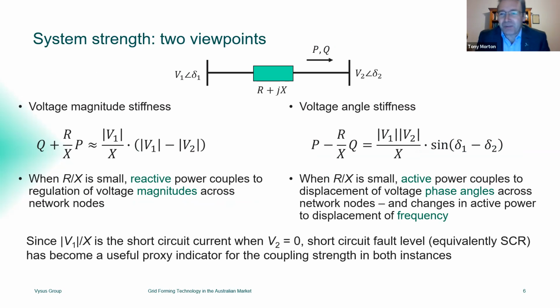So I guess we can then look at system strength itself using two viewpoints. Just looking at this for a typical branch in a network, we've got two voltages at each end of the branch, and we've got a certain branch impedance. And we can look at how the power flow on that branch relates to characteristics of those endpoint voltages. And this gives us different measures of the stiffness of the network relative to the change in voltage that you get for a certain change in power flow.